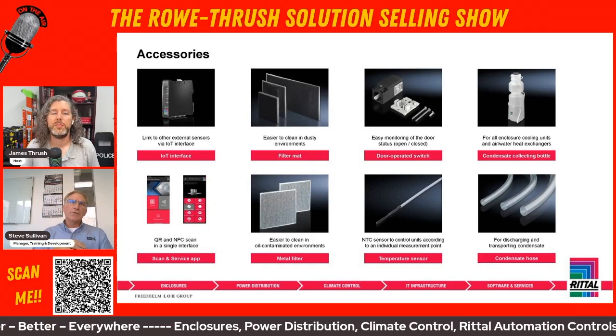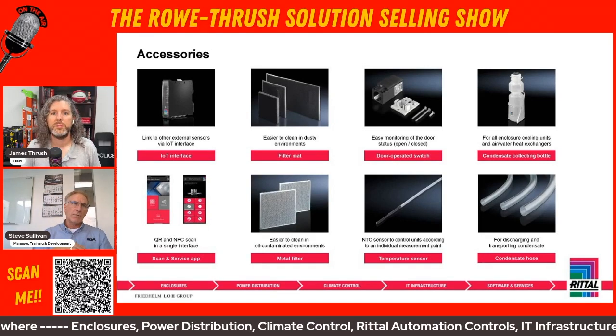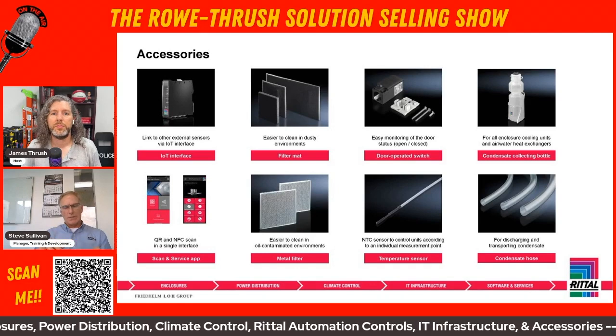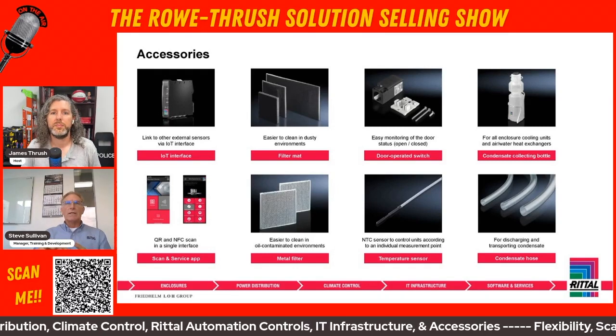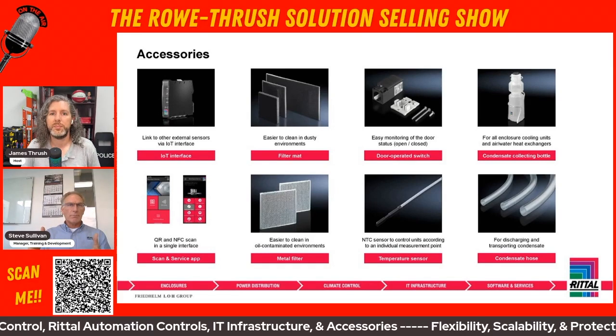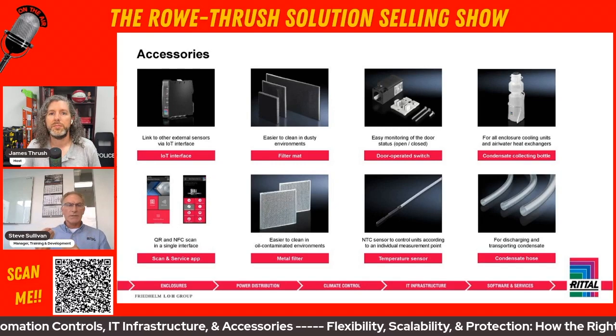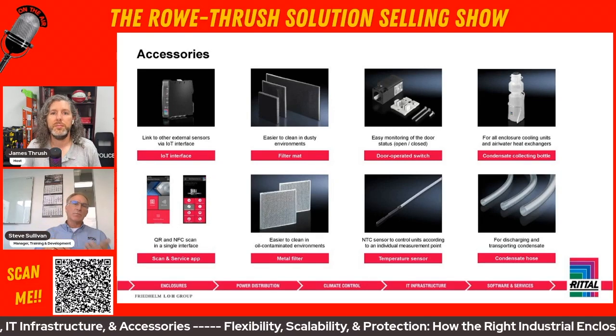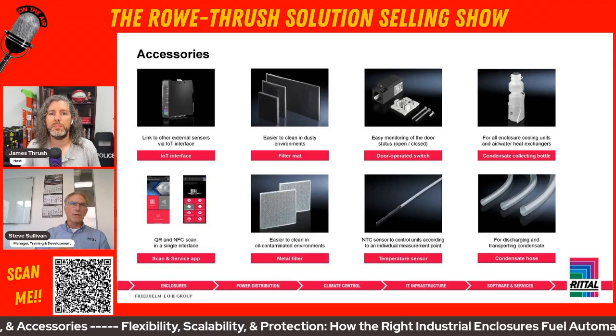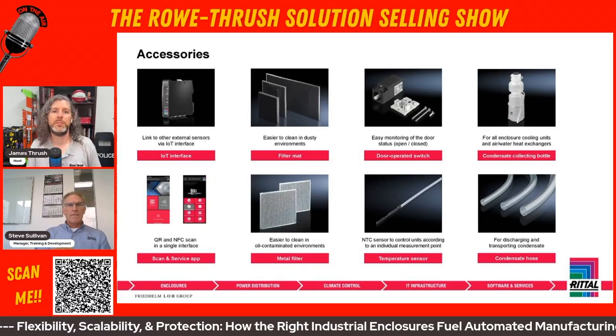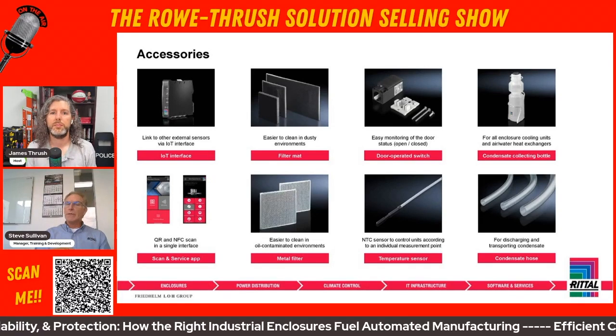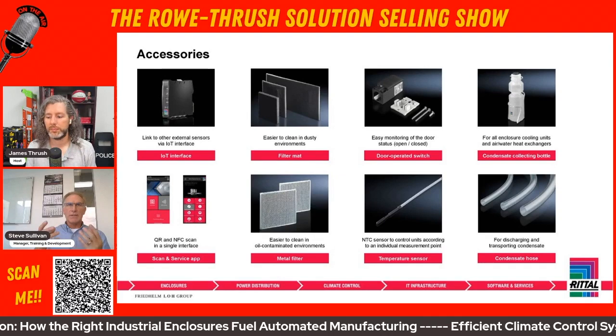Filters and understanding the environments that the AC unit will be deployed in, because you have metal filters that are good in oily environments, but they're not good in fine particulate. And then you can have disposable or polyurethane filters that are good in most environments, but not oil, because then they become saturated.